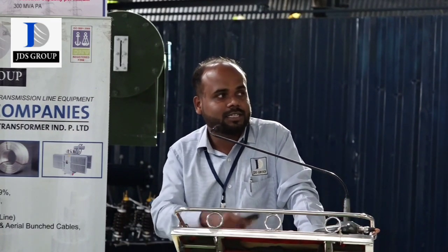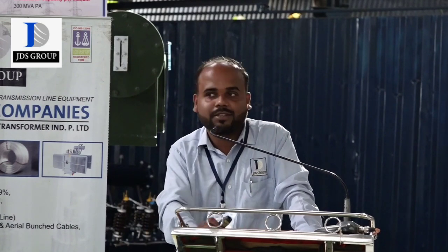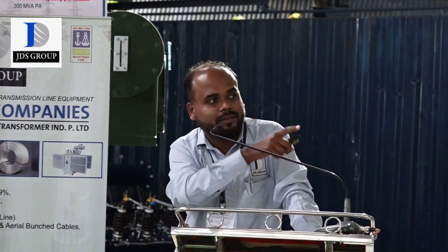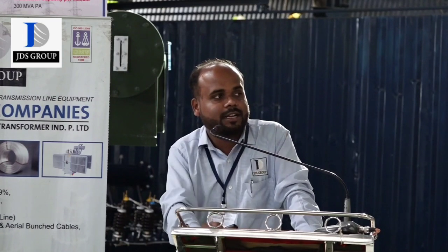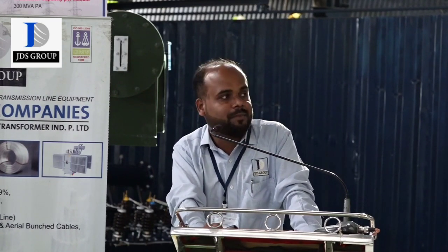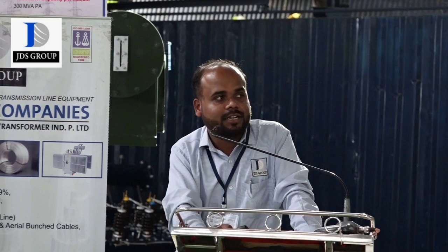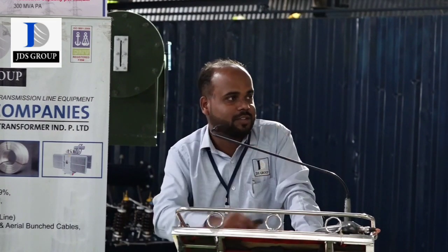After the load loss test, this is the image of a 5 MVA power transformer, in which on the HV side we have provided the rated current of 87.47 ampere, with the LV side short circuited, and an additional OLTC has been attached to the transformer.